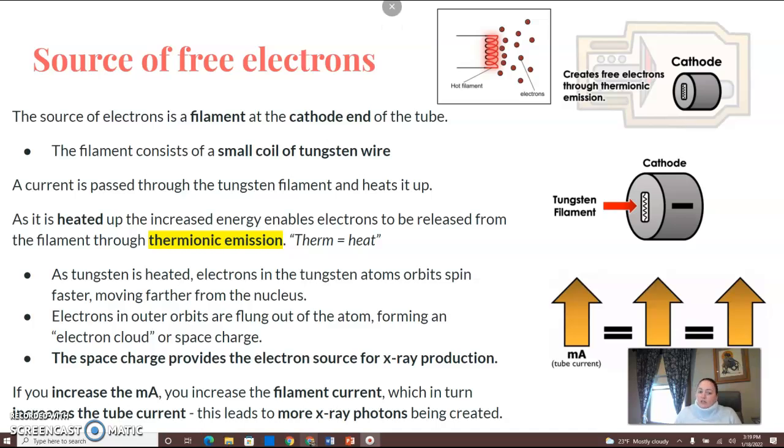If you increase the mA, you increase the filament current, which in turn increases the tube current. This leads to more X-ray photons being produced.